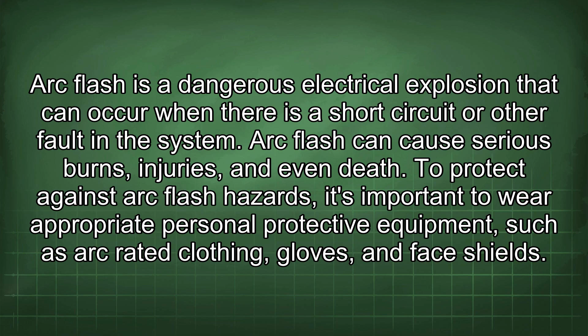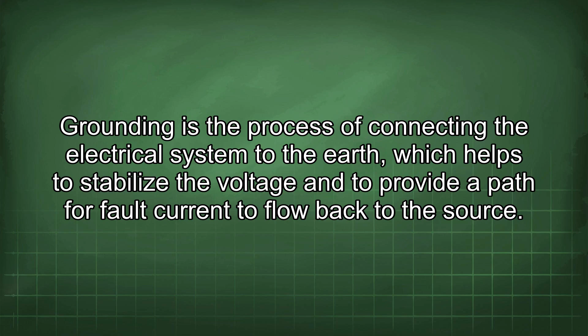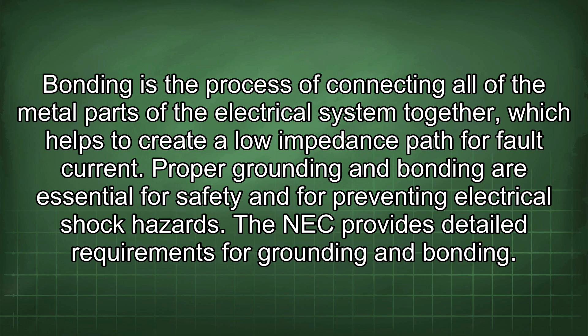When designing and installing electrical systems, it's also important to consider the grounding and bonding requirements. Grounding is the process of connecting the electrical system to the earth, which helps to stabilize the voltage and to provide a path for fault current to flow back to the source. Bonding is the process of connecting all of the metal parts of the electrical system together, which helps to create a low impedance path for fault current. Proper grounding and bonding are essential for safety and for preventing electrical shock hazards. The NEC provides detailed requirements for grounding and bonding.